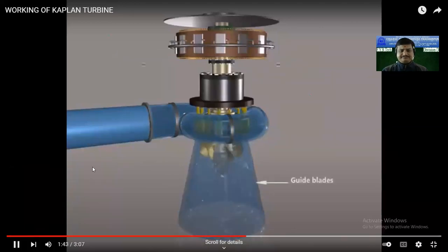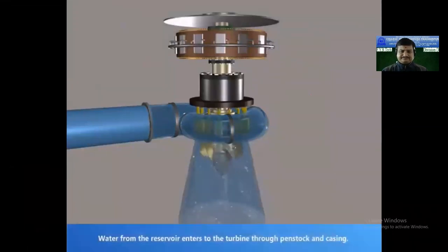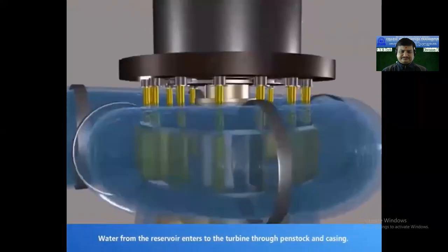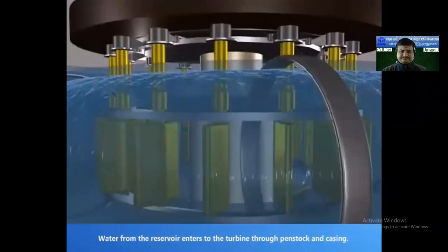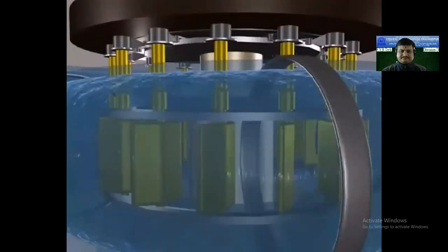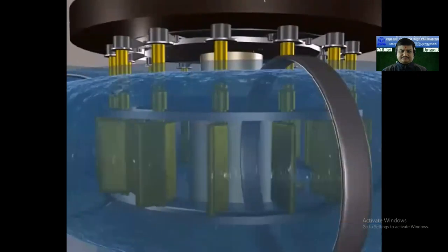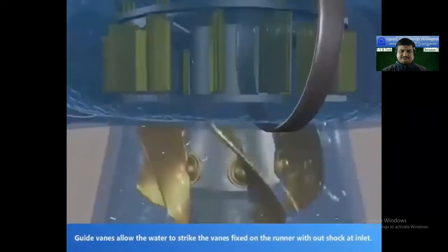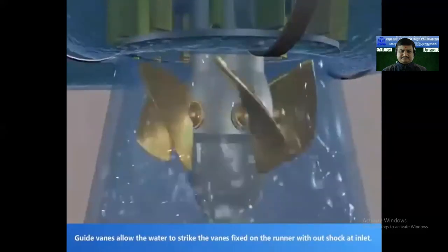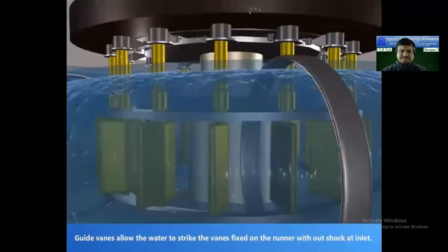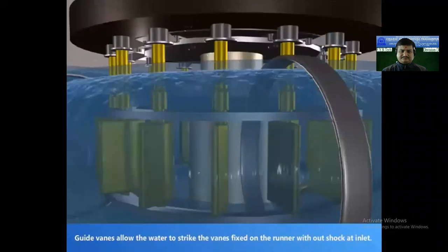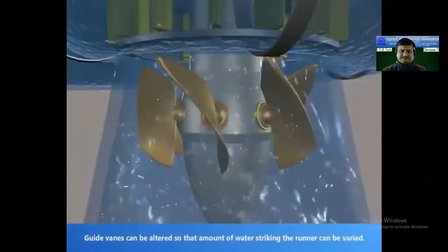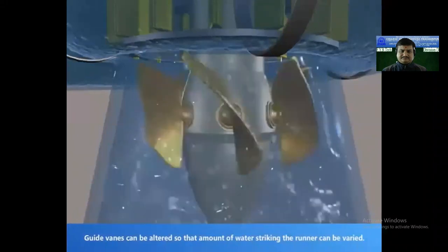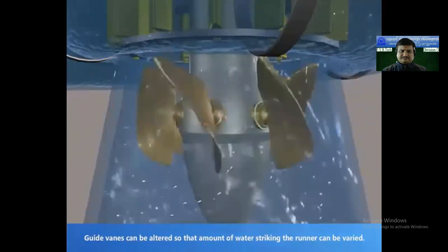turbine. Guide blades. Water from the reservoir enters the turbine through the penstock and casing. Guide vanes. Guide vanes allow the water to strike the vanes fixed on the runner without shock at inlet. Guide vanes can be altered so that the amount of water striking the runner can be varied.